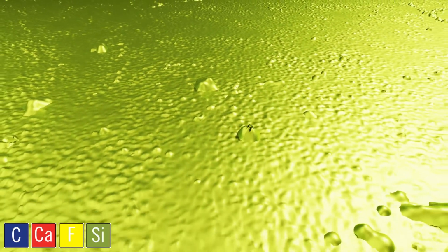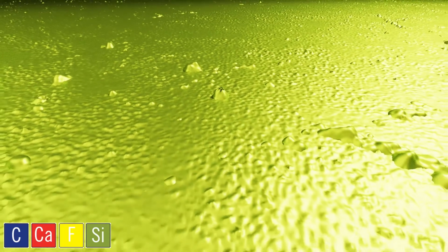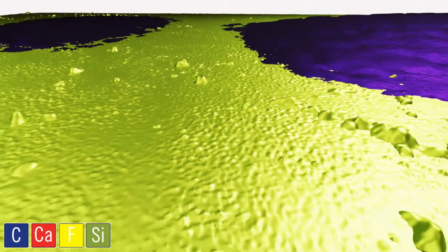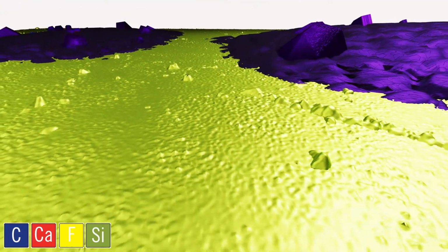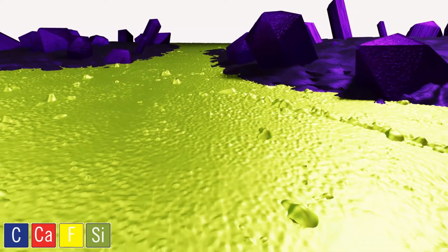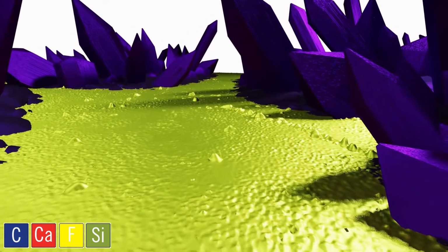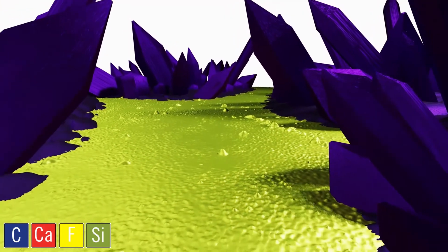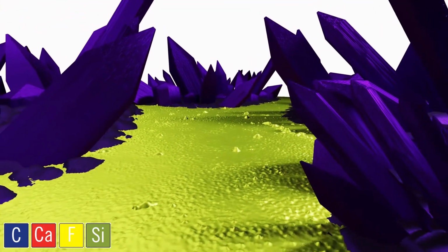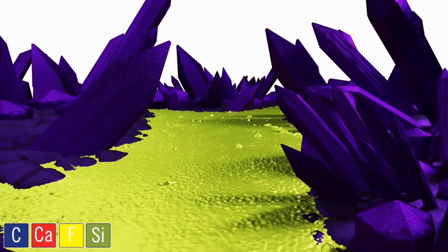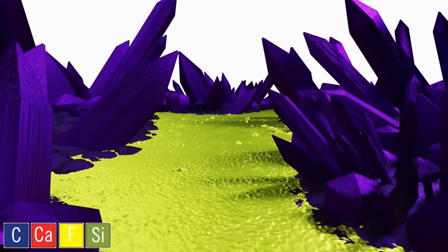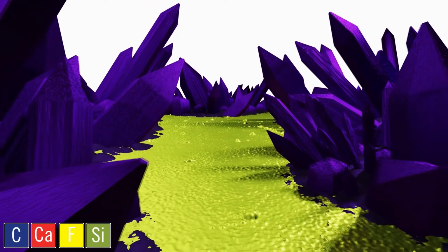The site already knew that they had the potential for silica scale, and they were dosing an antiscalant that targeted silica. However, the dose was based on an old analysis, and the silica levels in the water had since increased. After the formation of silica, due to the changes in element hydraulics and the creation of nucleation sites, calcium carbonate precipitated. As the site noted a loss in flow in their last stage, a clean was triggered.